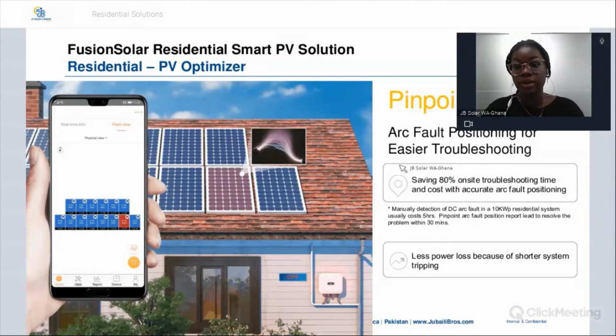Another advantage of the PV optimizer is that it can find your faults - arc fault positioning for easier troubleshooting. Normally you can't really pinpoint exactly where there is an arc fault. You can tell maybe it's on a certain string, but you can't tell exactly which module on that string it is. Especially for maintenance, this is very important. It reduces the time it takes for you to do your checks because it will scan the whole thing and then tell you, okay, this is where your problem is. Just go to this panel on the string and that's that.